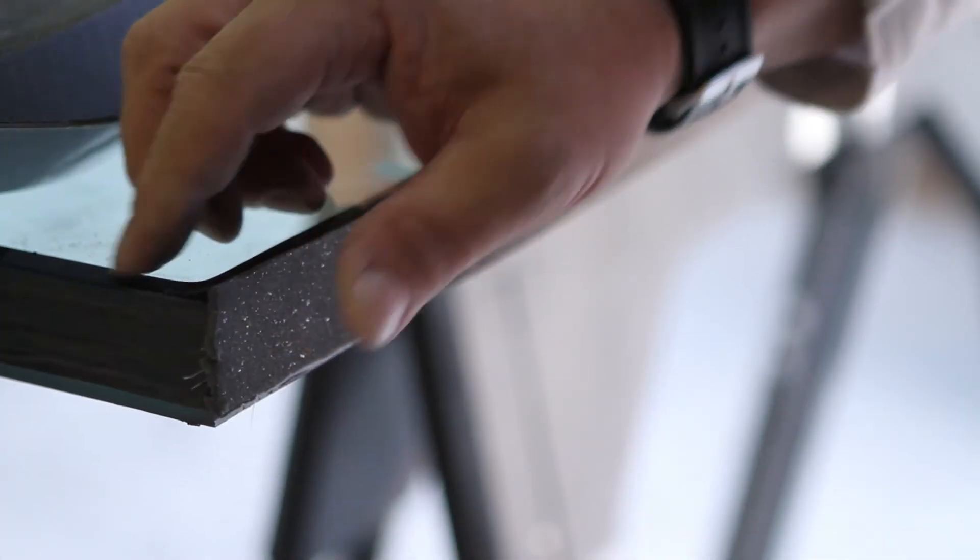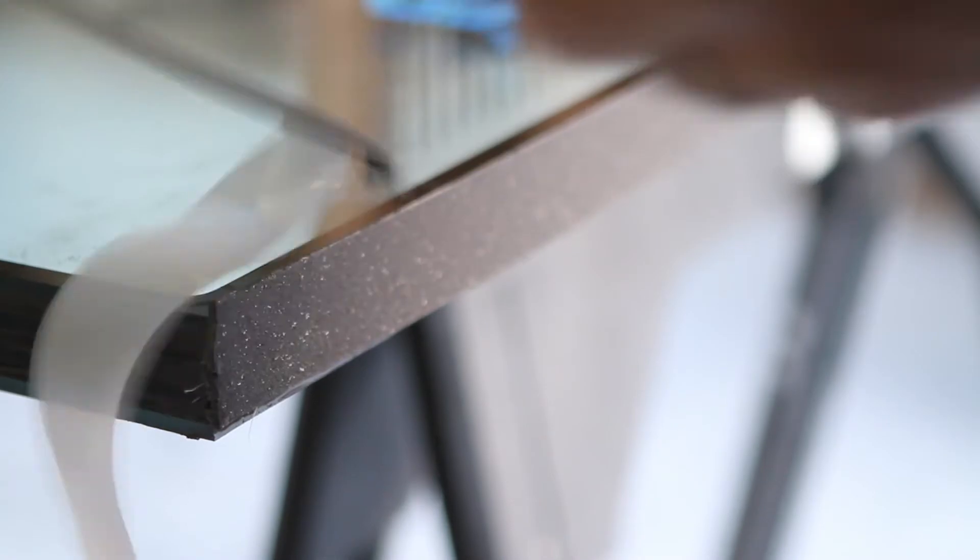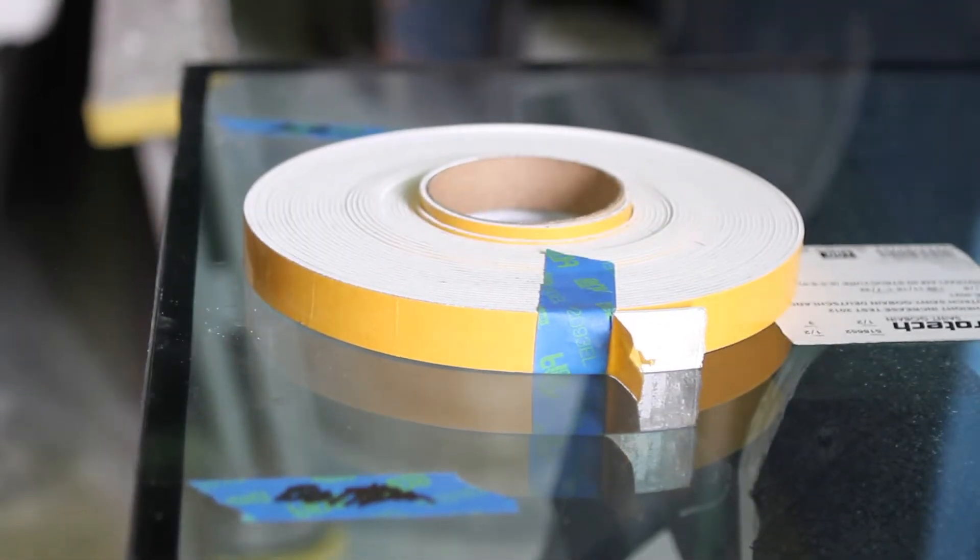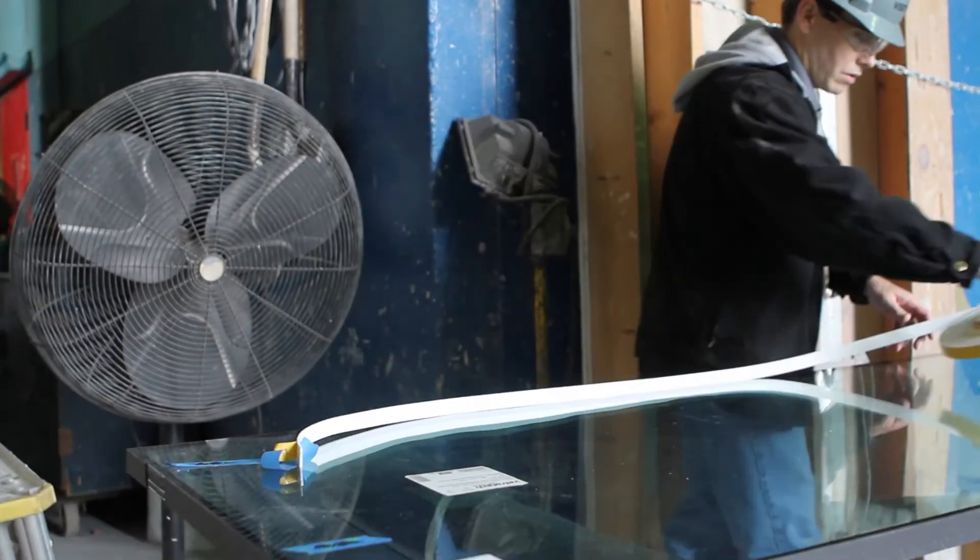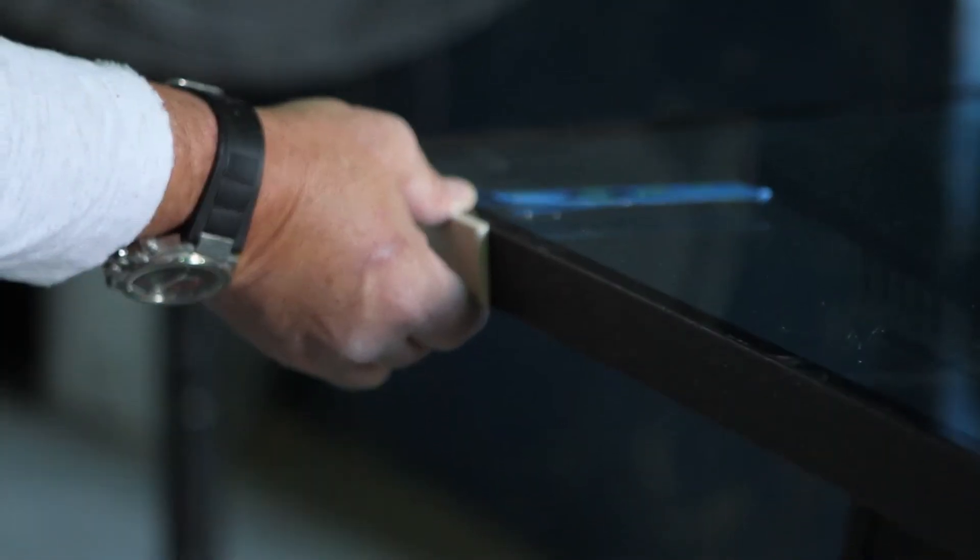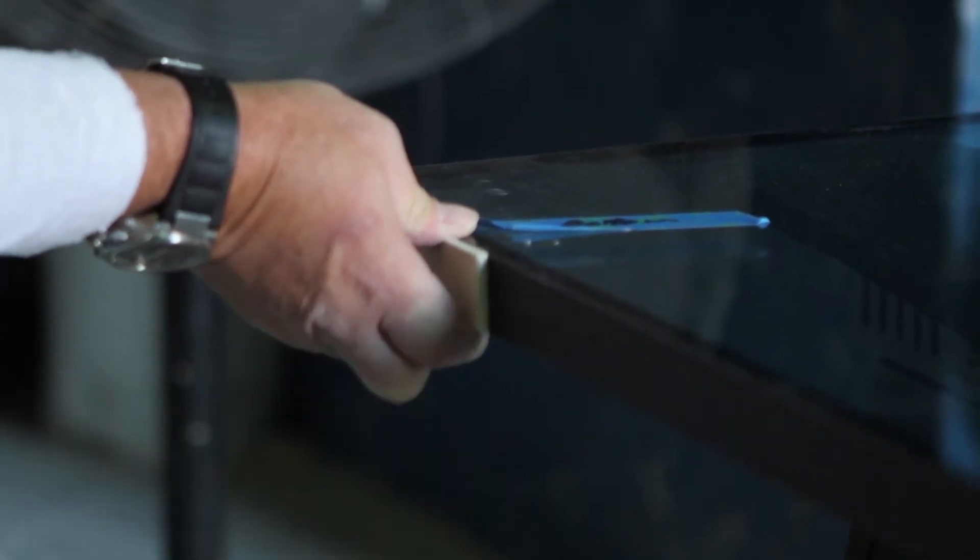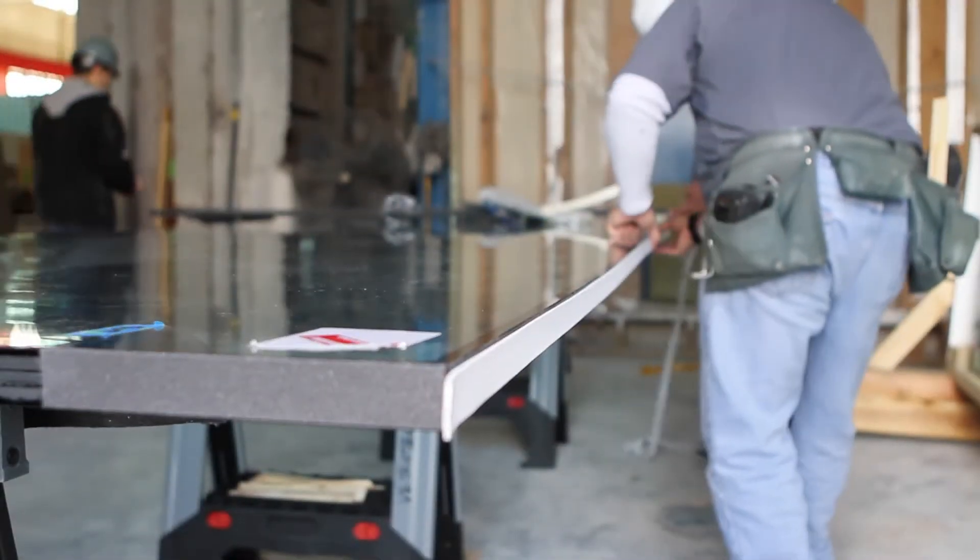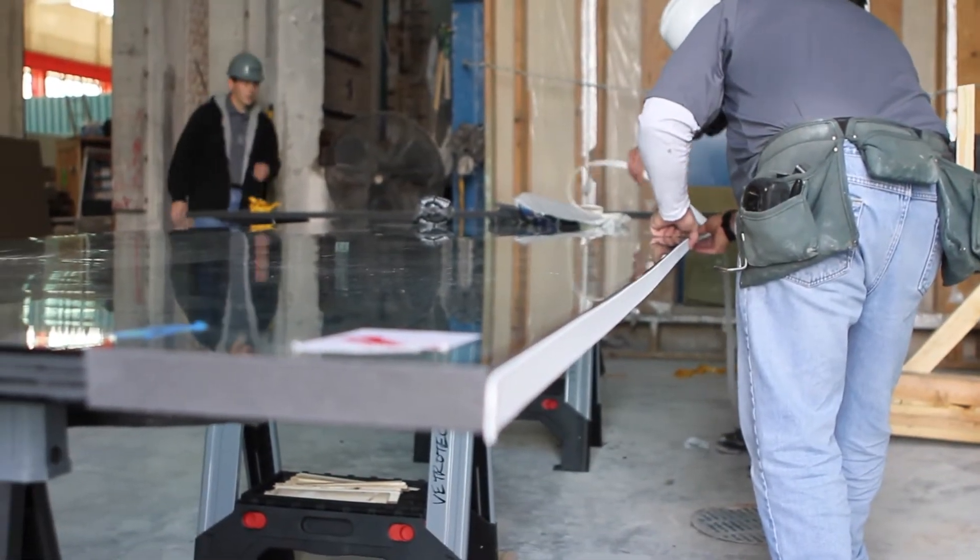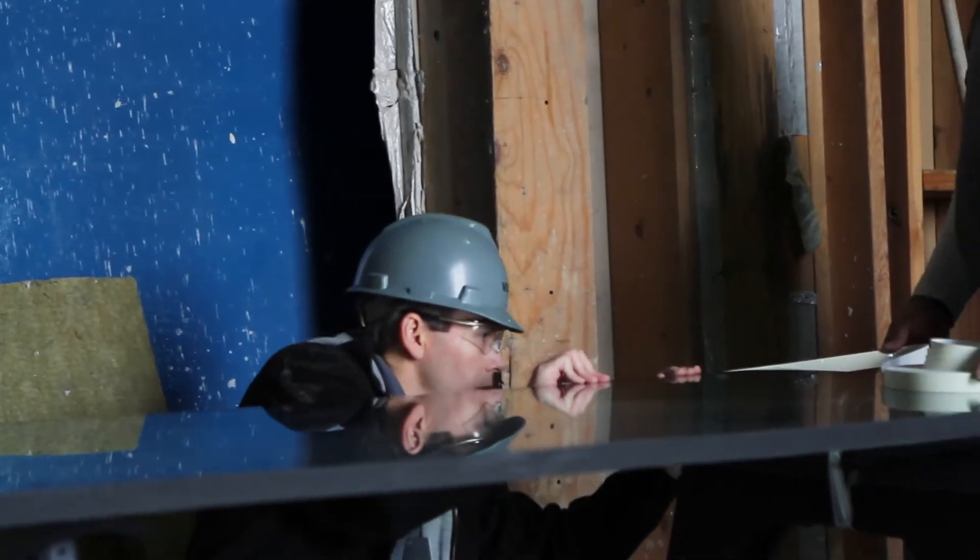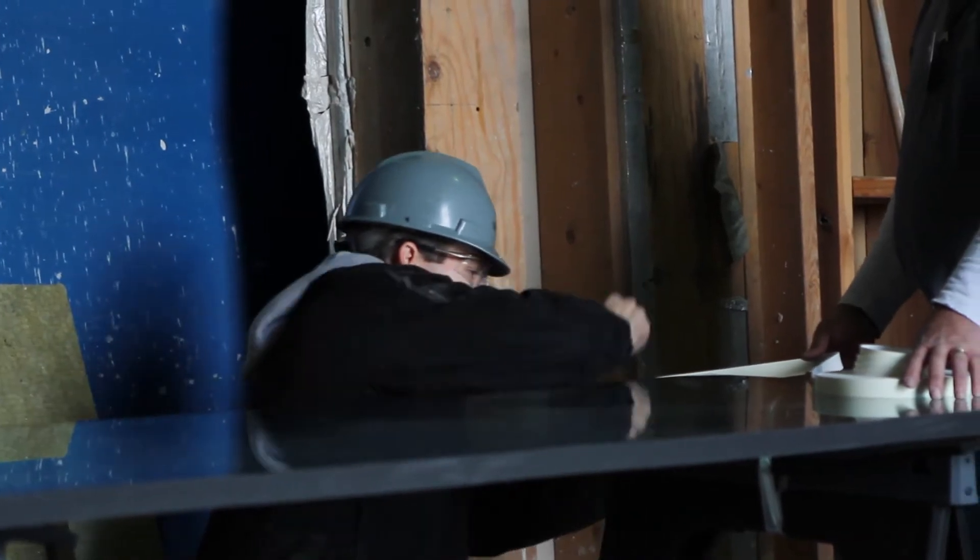Verify the alignment of the tape on the glass edge. The maximum recess at any point should not exceed 1/8 of an inch. Now apply the provided intumescent tape to butt joint glass edges. Be sure to cut around the locations at the quarter points for each pane, where the setting blocks at the sill will make contact with the glass. Verify the correct placement of all Vetrotech provided tapes on all glass edges.